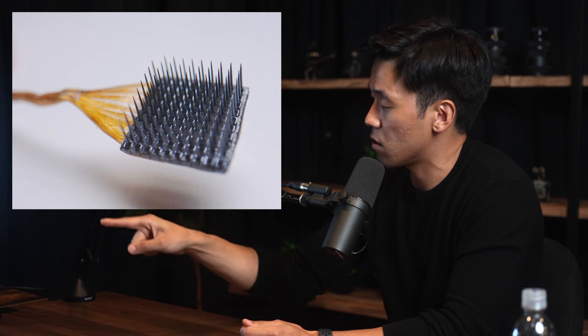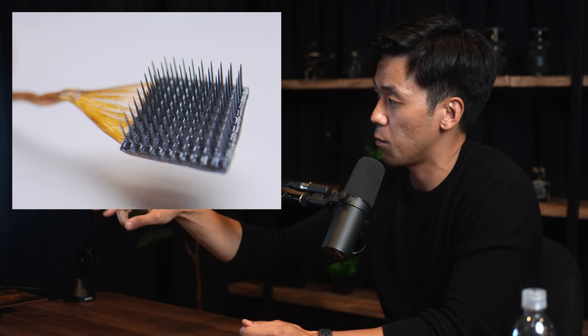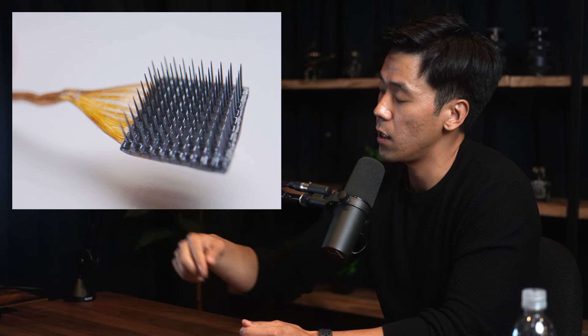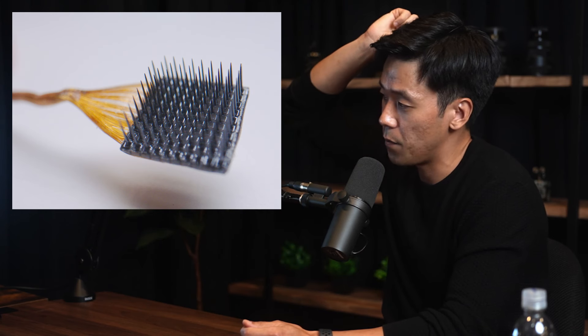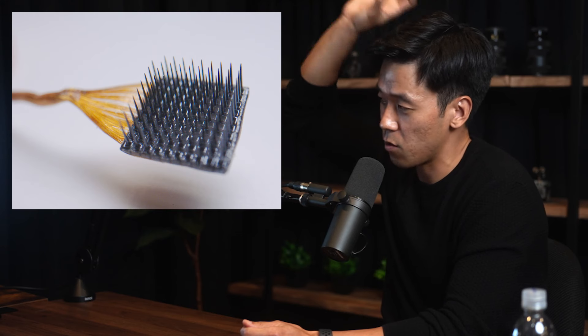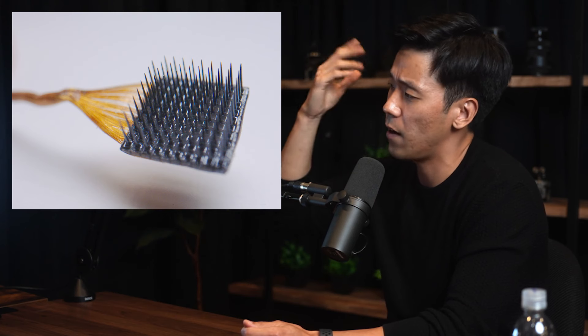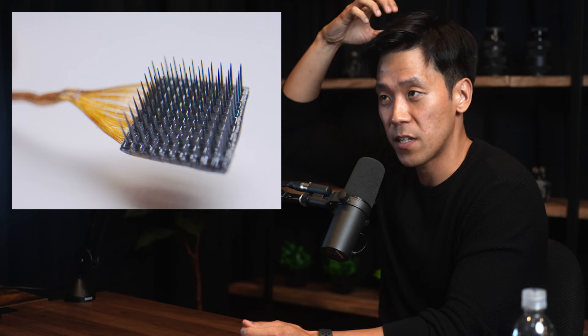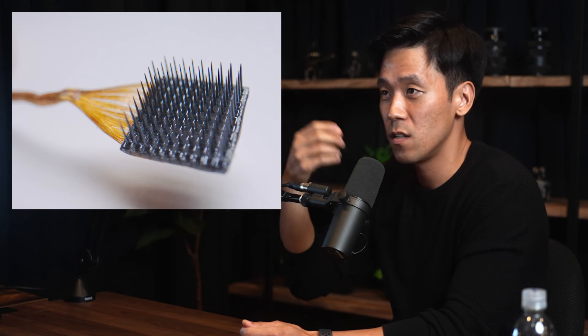The main key difference is the fact that there's no active electronics — these are just electrodes. There's a bundle of wire that exits the craniectomy, which then has a port that you can connect to for any external electronic devices. They do have a wireless telemetry device, but it still requires a through-the-skin port, which is actually one of the biggest failure modes for infection in the system.